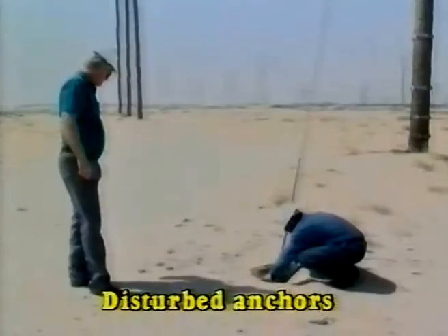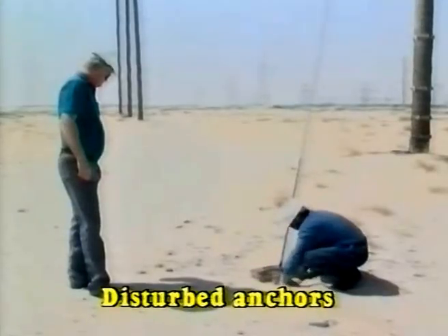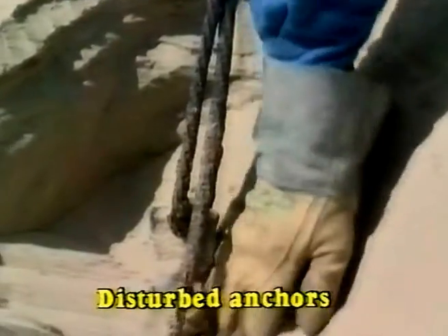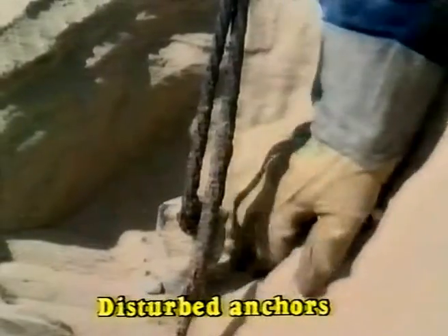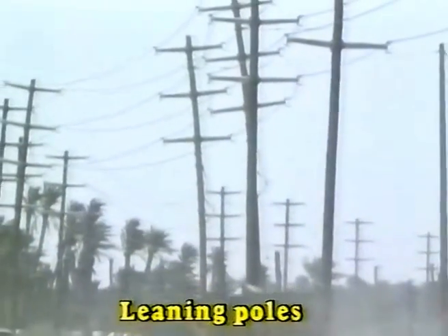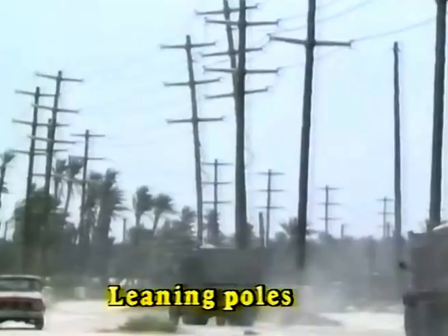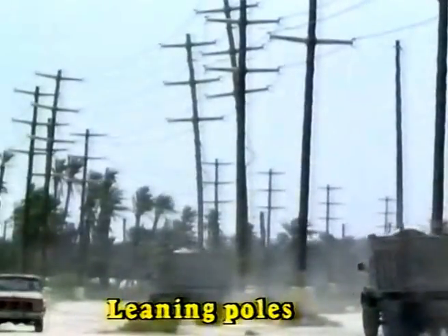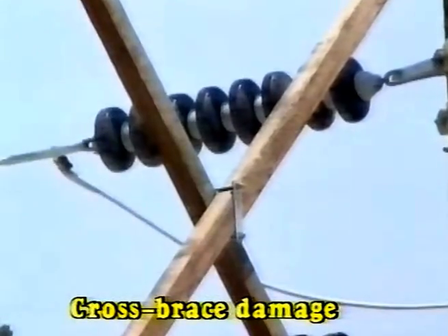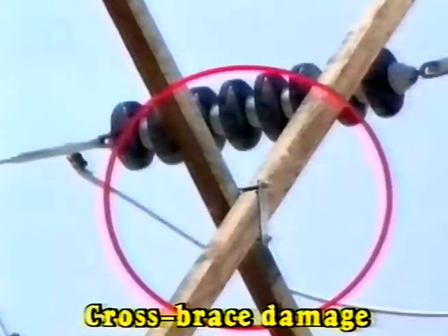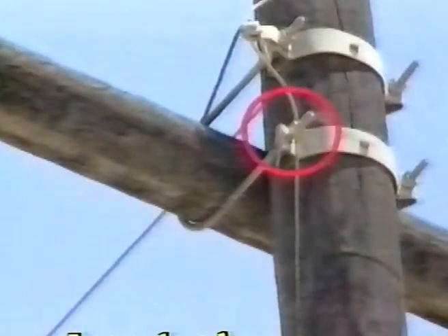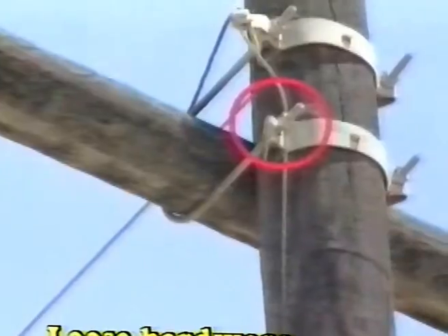Loose or broken guys. Disturbed anchors. Dig down to check for corrosion. Leaning poles. Note the approximate degree of lean. Cross brace damage. Loose hardware. Broken or flashed over insulators.